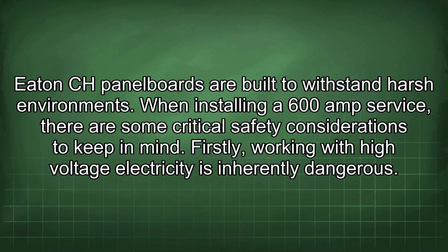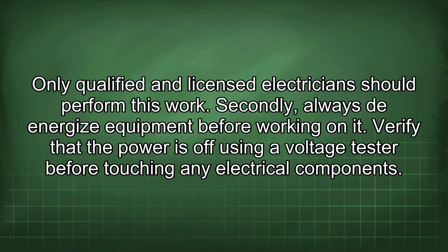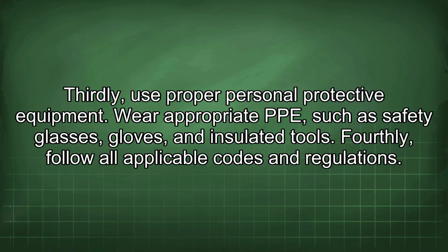When installing a 600 amp service, there are some critical safety considerations to keep in mind. Firstly, working with high voltage electricity is inherently dangerous. Only qualified and licensed electricians should perform this work. Secondly, always de-energize equipment before working on it. Verify that the power is off using a voltage tester before touching any electrical components. Thirdly, use proper personal protective equipment. Wear appropriate PPE such as safety glasses, gloves, and insulated tools.